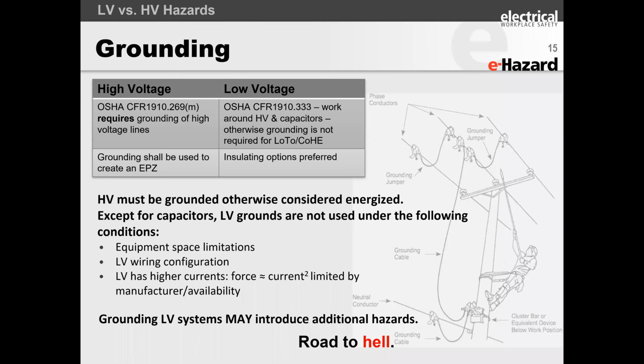Grounding shall be used to create an equipotential zone. Now folks, I don't want to get into a full equipotential zone discussion because I'd need an entire presentation for that. But let's talk about this as clearly as I can: whatever happens, all of these lines are connected to each other, connected to the area where this lineman is standing, and connected to the neutral conductor, which in turn is connected down to ground.